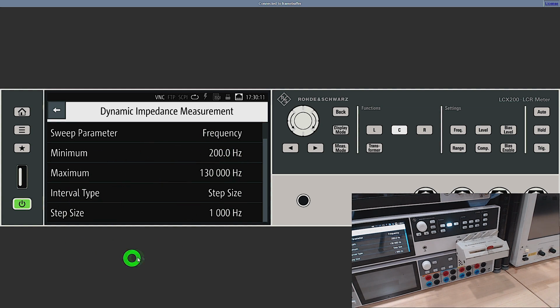One additional option I wish this sweep had is that it would allow you to specify whether the instrument should auto check the component after every step, essentially pressing this auto button after every step is complete. The advantage there would be that the instrument would at some point switch from inductance to capacitance measurement, so that we can get the complete curve, both of those parameters measured. As it stands, it's going to try and measure capacitance, which of course doesn't work at some of those frequencies. It's going to have a gibberish equivalent model. However, we're going to be able to discover the resonance by looking at RP or RS, and that's going to tell us everything we need to know.